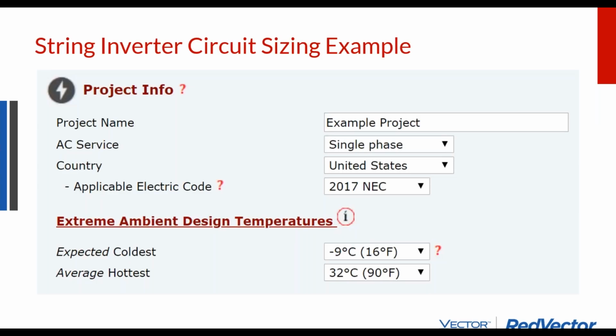So how that relates to solar design, very briefly, because nowadays all this stuff is done by design software: you put in the manufacturer design software, you put in your location, and then you're designing around your coldest temperature. And then on the hot end, your inspectors will look at the coldest temperature on record in your area and say you got to design to that low end temperature, but they're not going to make you design around the hottest temperature on record, because again, on the hot end, your voltage is decreasing, so you're not going to have a problem there. And even though your amperage is increasing at hot temperatures, it's not increasing by very much.